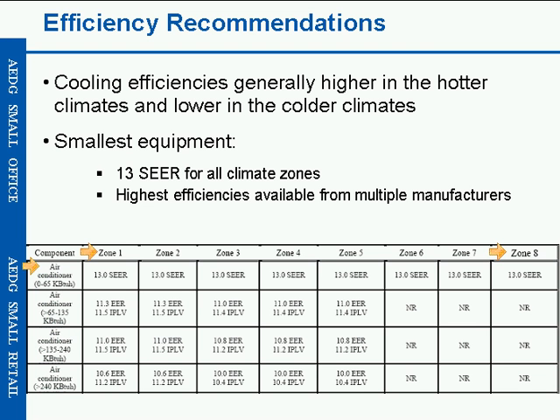For the smallest rooftop air conditioners, the ones from 0 to 65,000 BTUs per hour, there's a 13 SEER recommendation for all climate zones, and this is basically the highest efficiency available from multiple manufacturers. For the larger systems, the efficiencies are higher in climate zone 1 than, say, climate zone 5, and when there's NR, which refers to no recommendation, that refers to using the code minimum efficiency for that system type. And so these are the recommendations in the small office design guide and the small retail design guide.